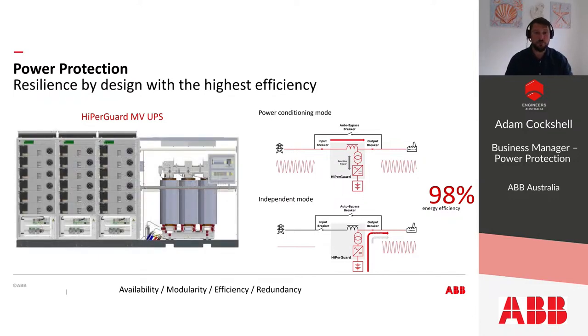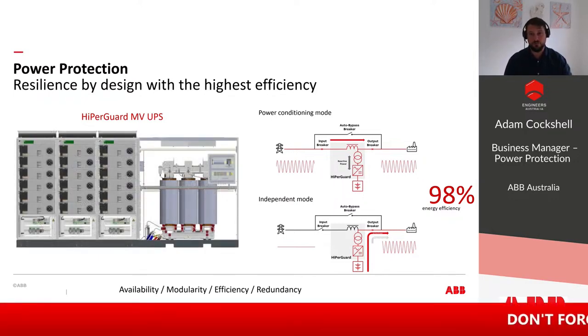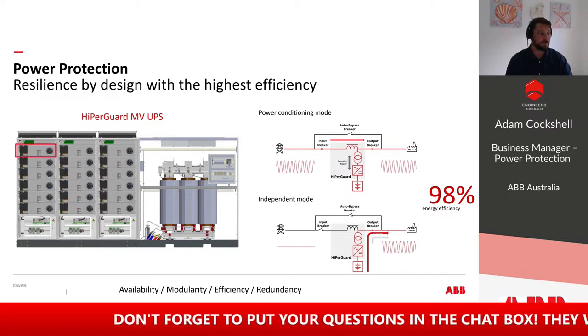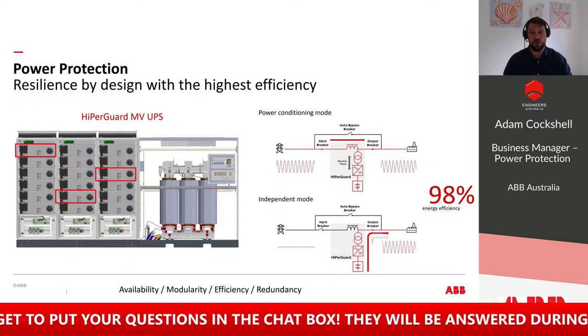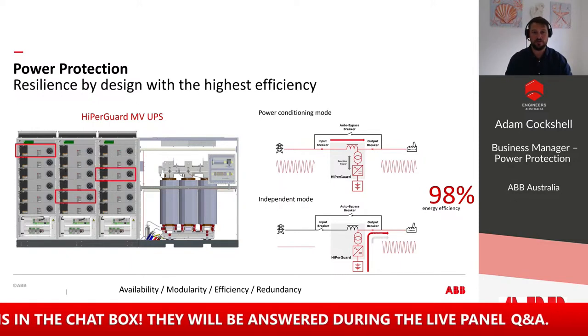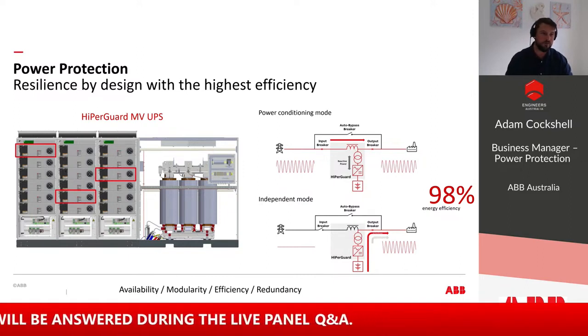The HiPerGuard's 2.5 MVA system output is designed with redundancy in mind. With ABB's modular approach to power protection, the HiPerGuard delivers on its 2.5 MVA output with 1, 2, or 3 inactive modules having no impact to the output capacity. Combined with a wide range of modern energy storage, ABB's HiPerGuard provides autonomies from a few seconds to many minutes.